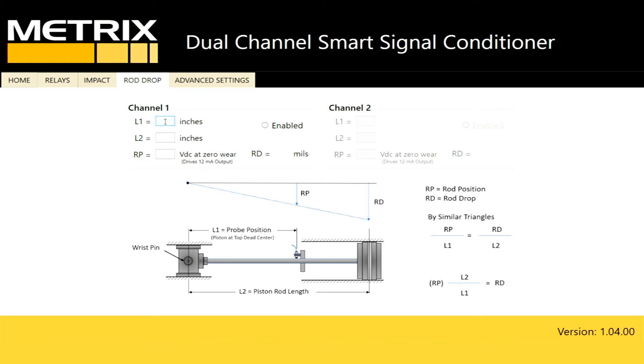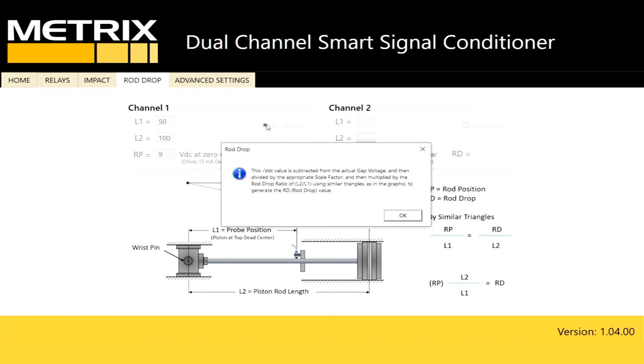Today we're going to simulate those distances and say L1 is 50 inches — I can do this in metric units just as well — and L2 is 100 inches. So the L2 over L1 ratio is a factor of 2. I've measured my gap voltage before we started and it's at 9 volts gap, so I'm going to go ahead and put that 9 volts in. Then I'll enable the system and it will tell us we're going to use similar triangles and multiply our displacement units by a factor of 2, since that's our ratio.